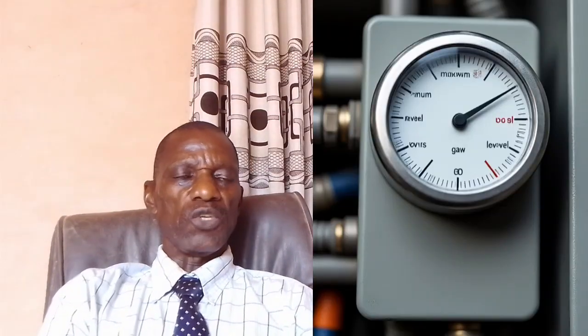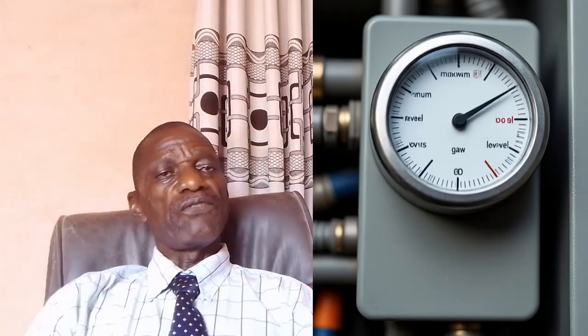That's the pressure meter. You will see the green, which is tolerable. That is within the operational value. Then, if you see it pointing at yellow, that means it has dropped. We now have low SF6 gas, which is not normal. The breaker can still be operated even with the low SF6 level. Then, when you see red, that means it has gone into lockout. There will be no mistake of you closing that breaker, because the gas will not be effective enough to quench the arc, and so the breaker will not even close because it will lock out.